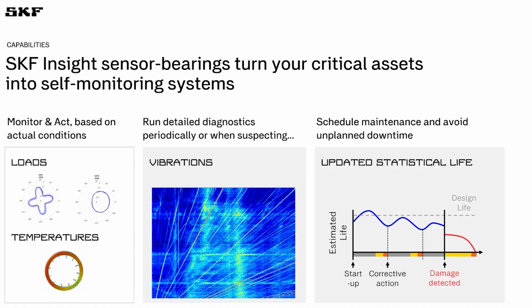Now, there's a lot of detail in this, but what's really the message here is that we can generate a crystal clear picture of what's going on with the machine, much more clear than with our conventional condition monitoring equipment that utilizes a vibration sensor on the outside of the housing. We are inside the machine, and this picture is compiled from multiple sensing points inside the bearing. So that generates a very high signal to noise ratio, and that is the starting point for a detailed diagnostic. That can be done periodically or when suspecting some troubles or on a continuous basis. It's an excellent way to make sure that the critical asset is running in a good condition.